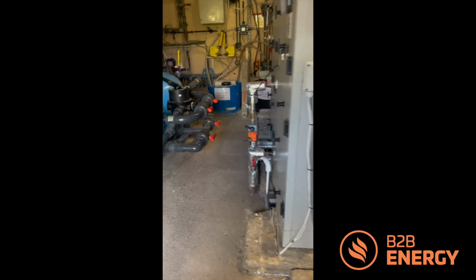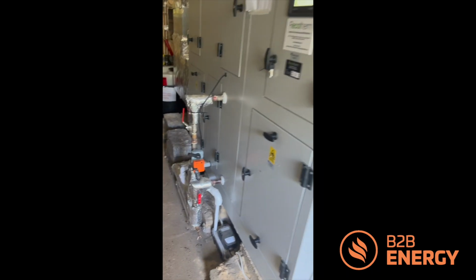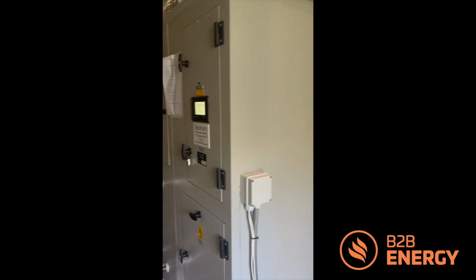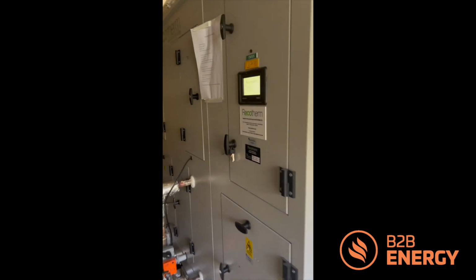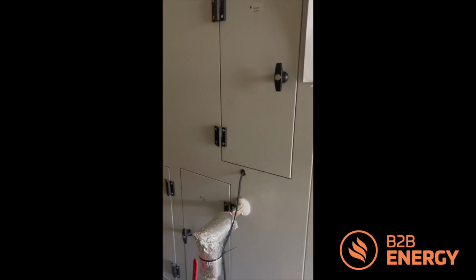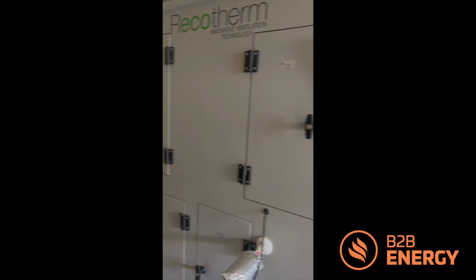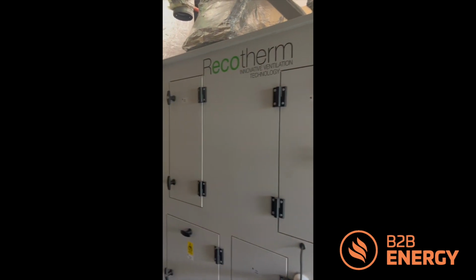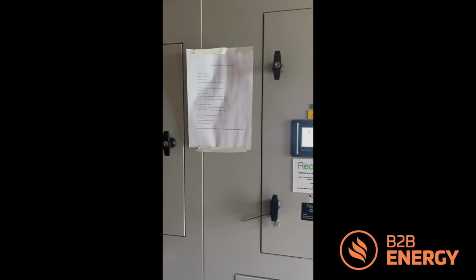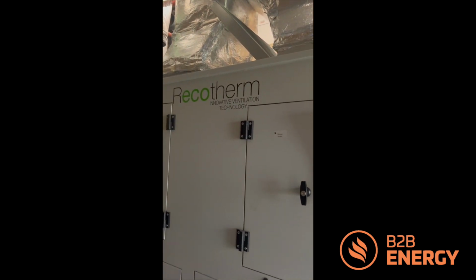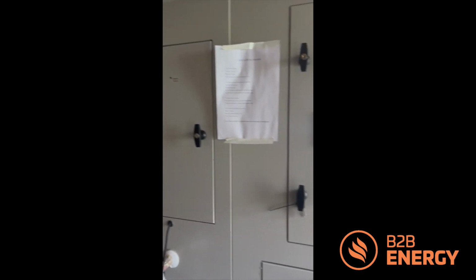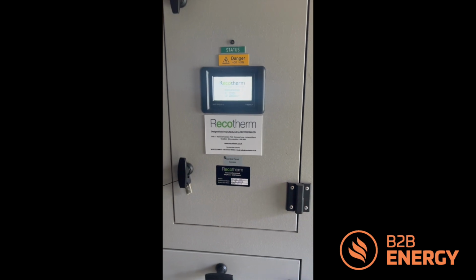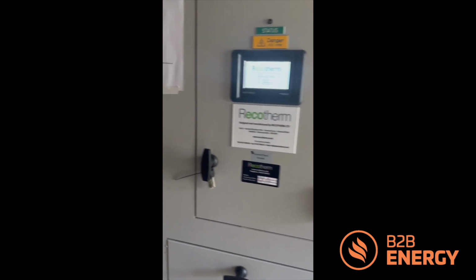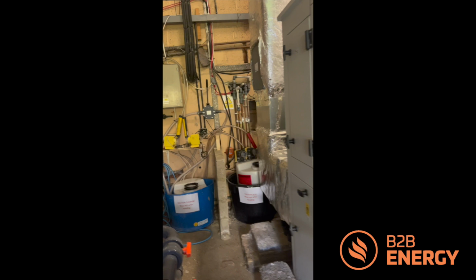First of all, we're just going to identify whether there's any control panels around and what control systems are. You can see this is a Recotherm system, and this provides control for the humidifier system and the heating around the pool itself. You can see here it's clearly being controlled by a Trend system, so it's got a Trend built-in BMS system that controls it. That's the temperature, and then we're going to focus on the temperature of the pools themselves.